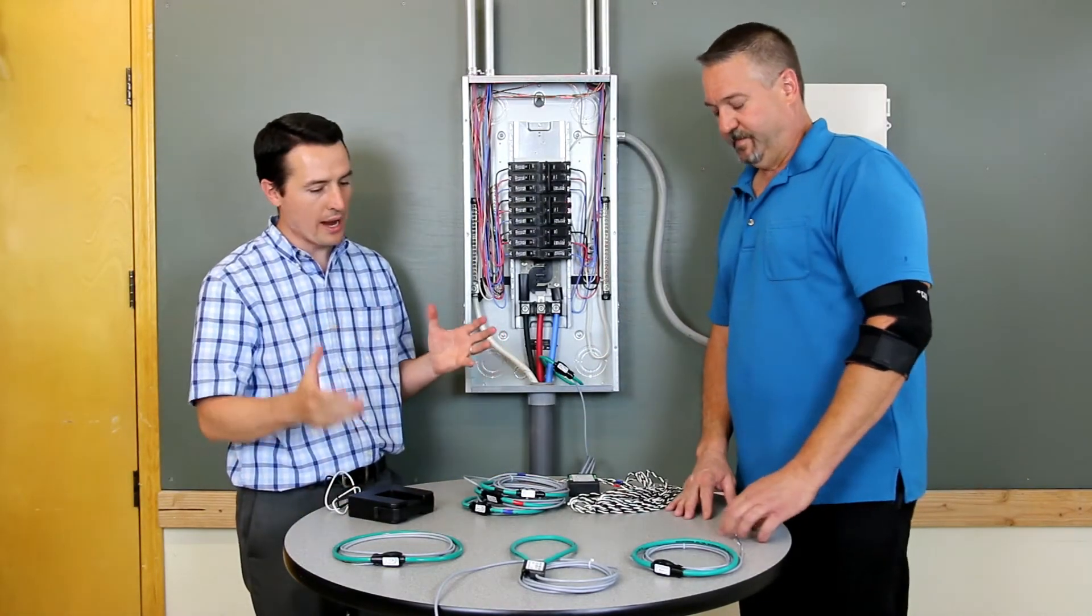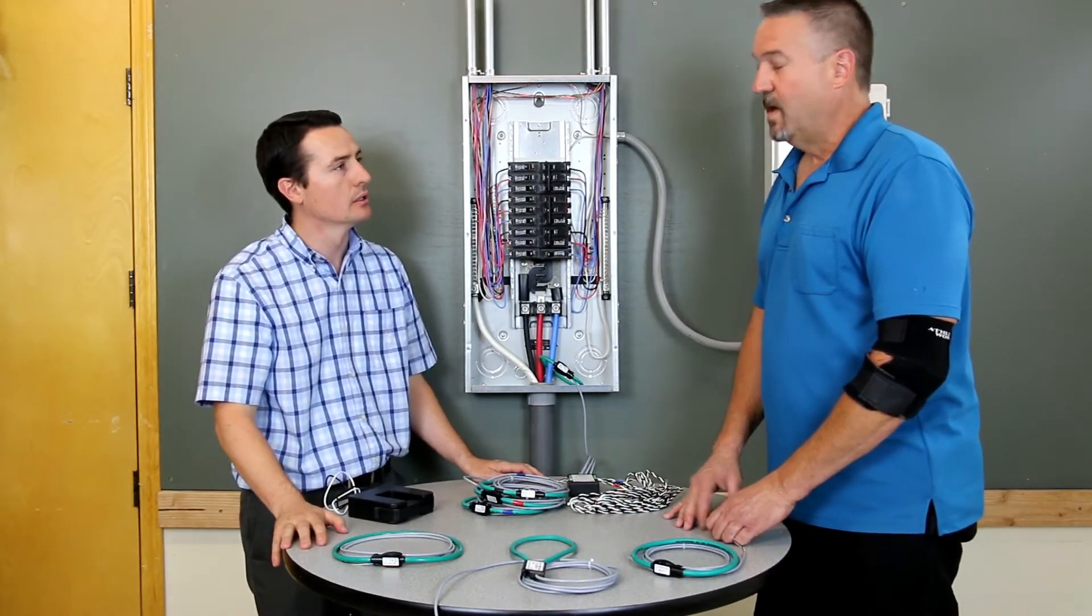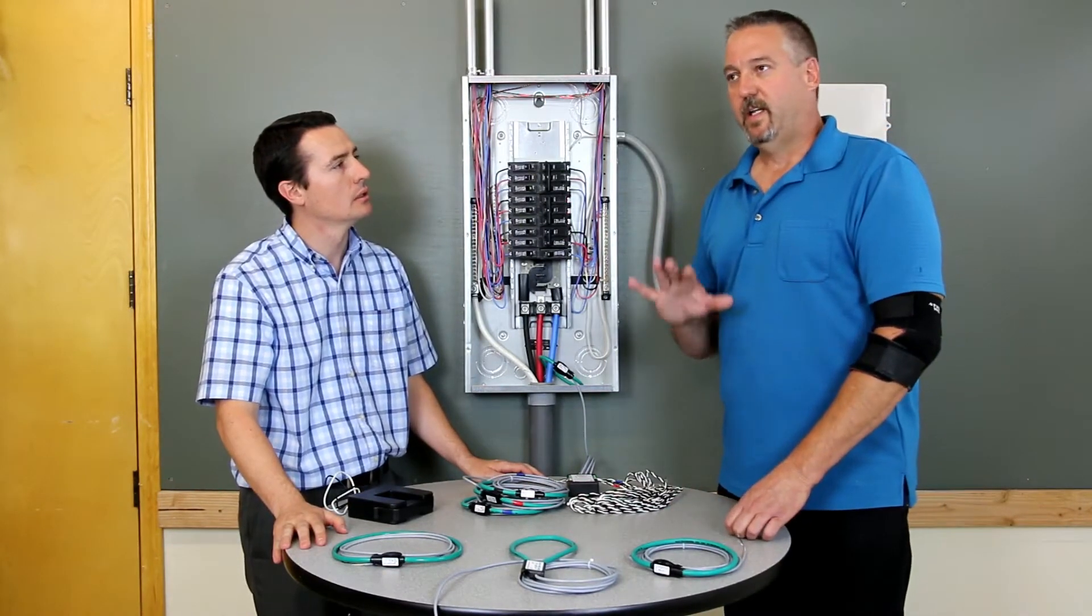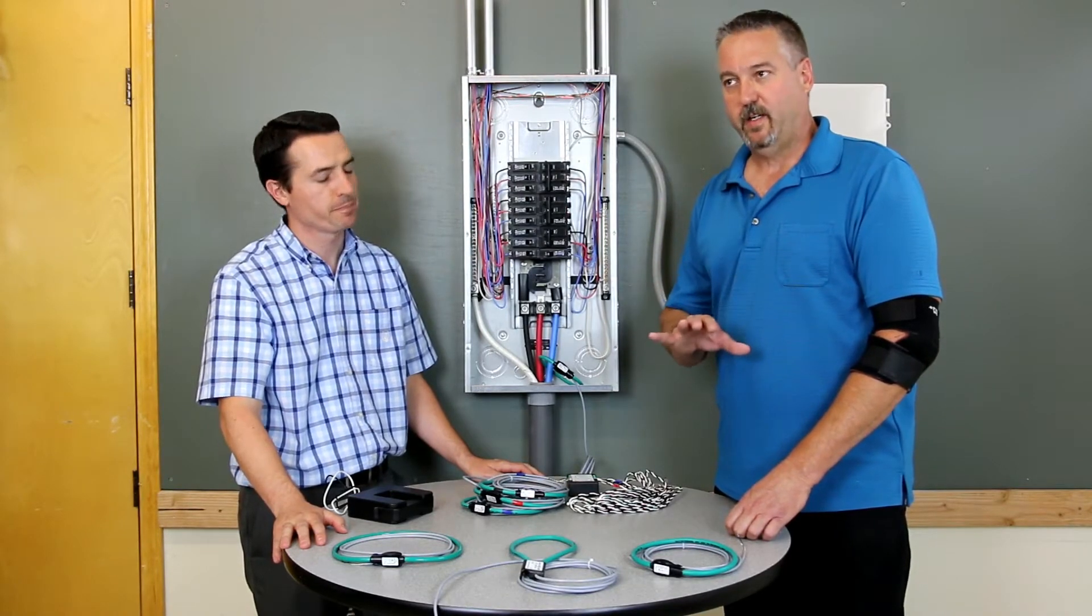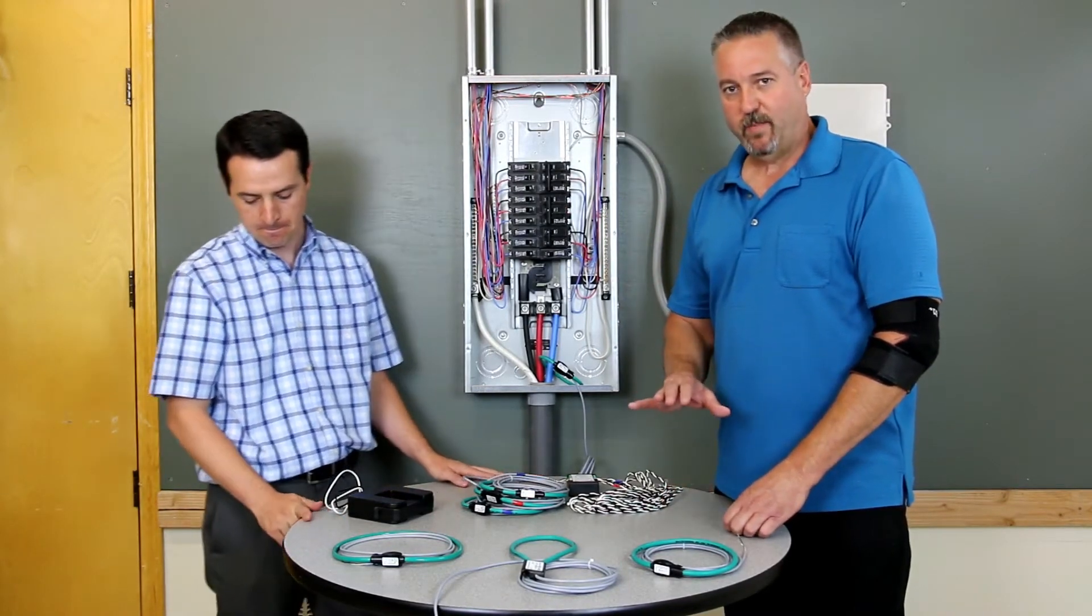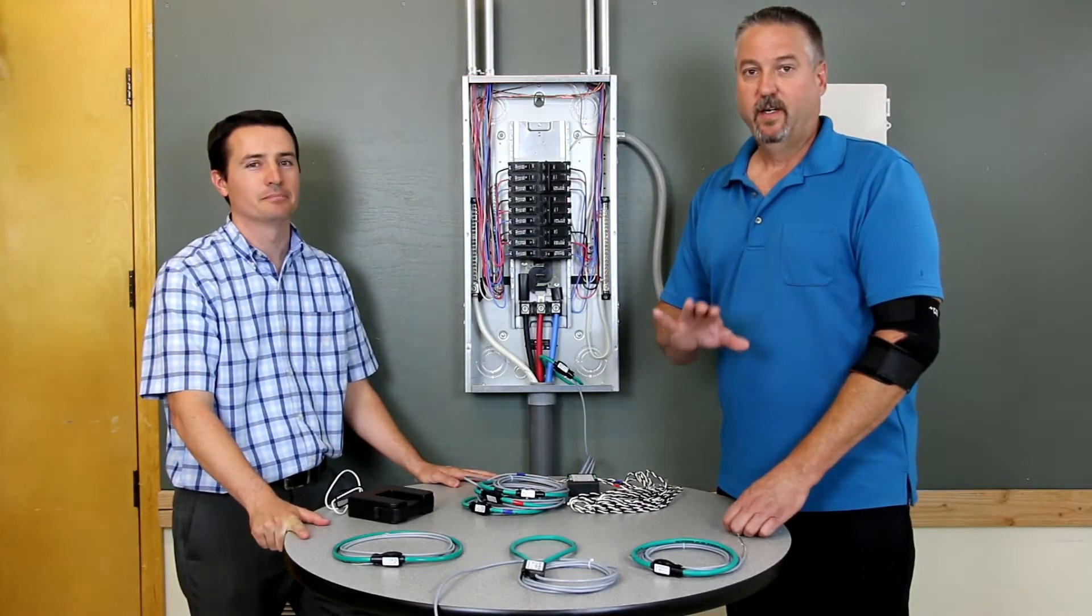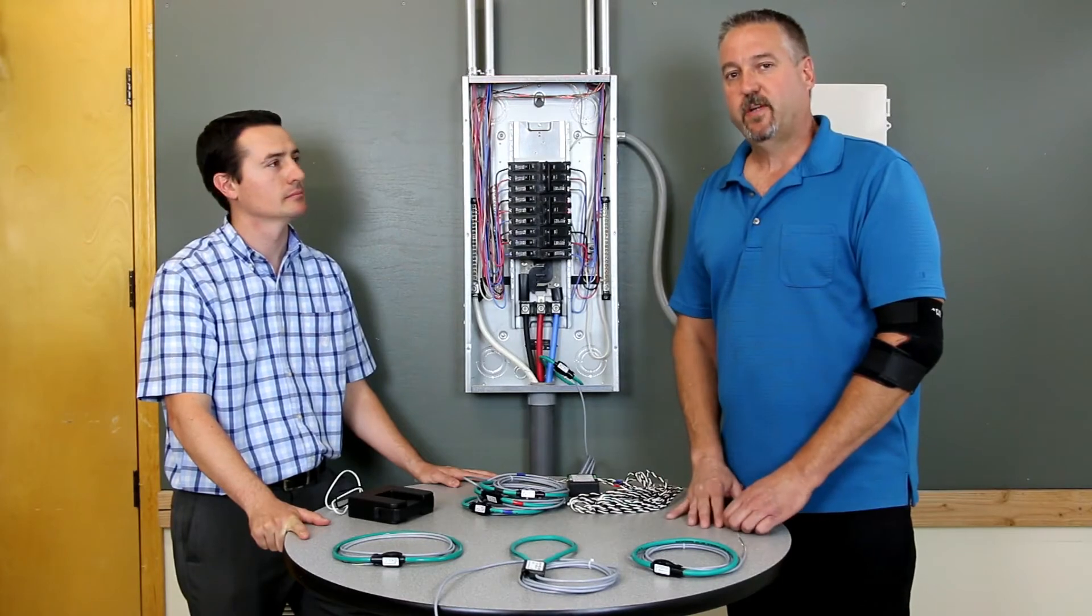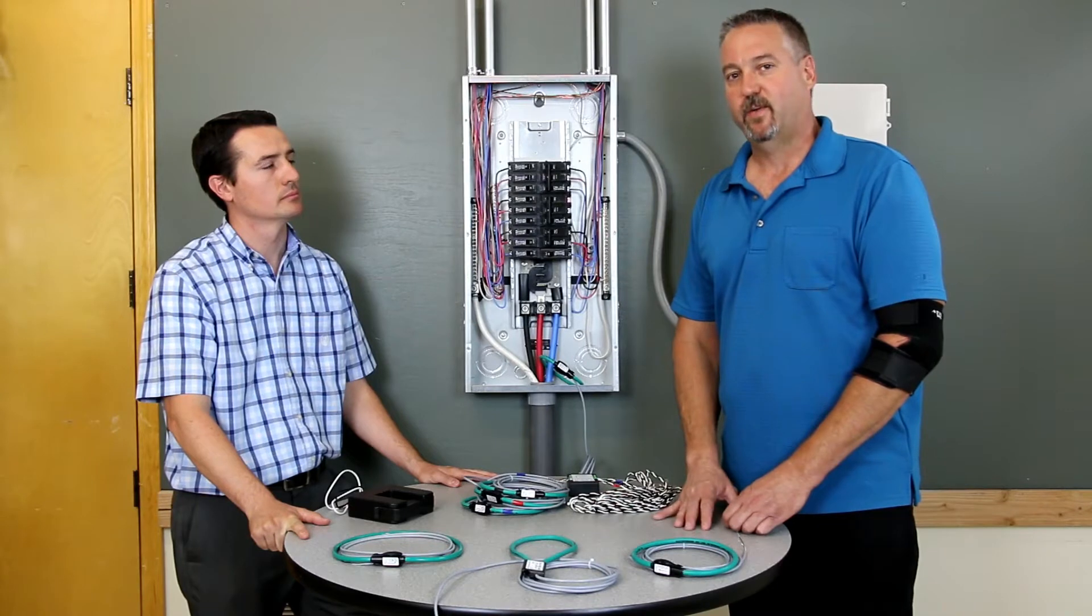And why do I want to monitor my power with a Rogowski coil or a CT? Power monitoring is critical in the area of power savings. It's also commonly used to monitor equipment in a manufacturing facility or even a grocery store to look for the trends in the power consumption. If a piece of equipment starts to increase in its power consumption you know something is starting to go wrong.